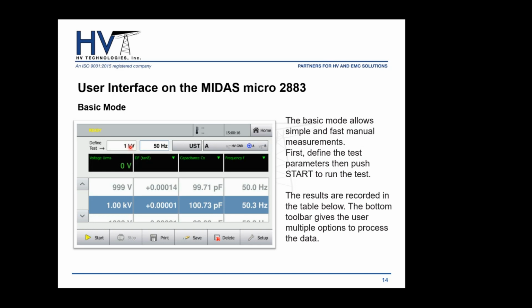So you go ahead and select first your test voltage. You select your test frequency. Then you select your test mode. If we want to do interwinding, we do UST mode. And then by pressing this button here, you can choose whether you want your A signal cable to be included in the measurement, or your B signal cable, depending on how you do your test connections.